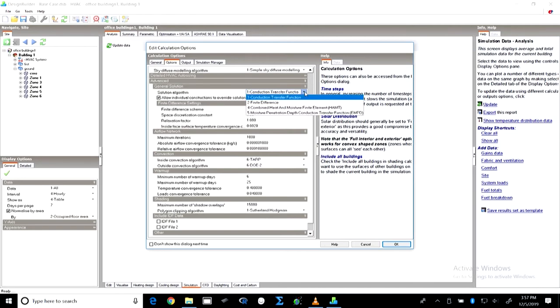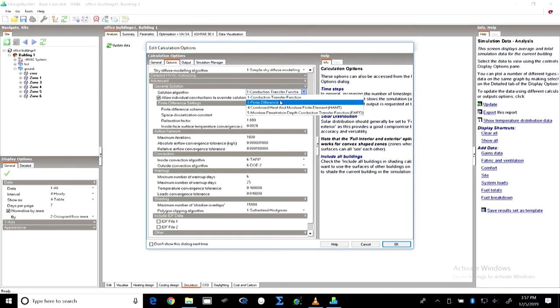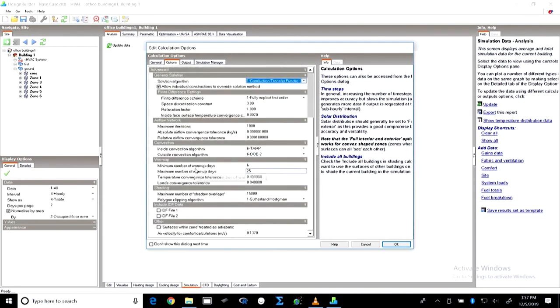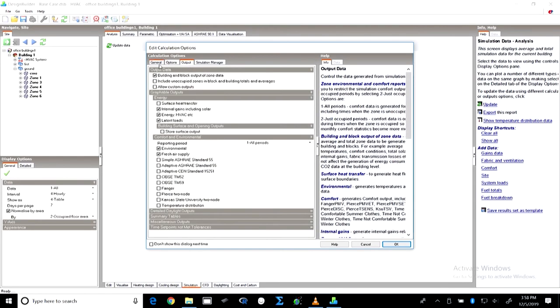In advanced settings we can look at the algorithms used for convection and warm-up periods. For now, for the base case we will keep most settings at default and keep the same for the proposed case as well. For the warm-up period, a minimum of 6 warm-up days is used before the system achieves target temperatures — these are days where the building is simulated so the structure gains enough warmth to account for heat exchange through the envelope. We can also define what outputs we require.